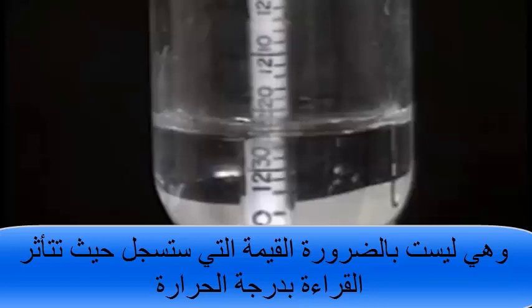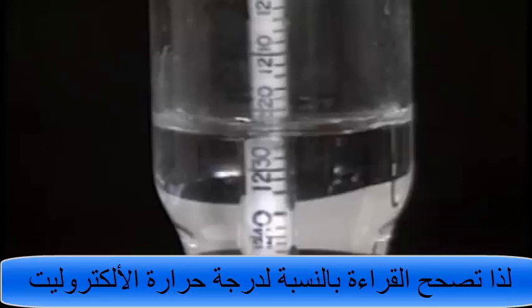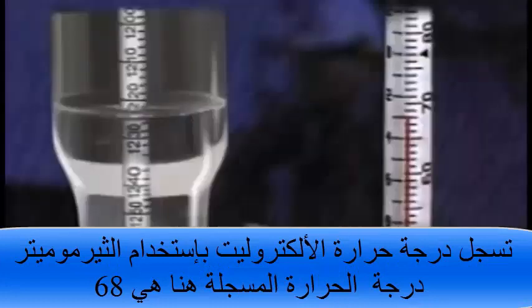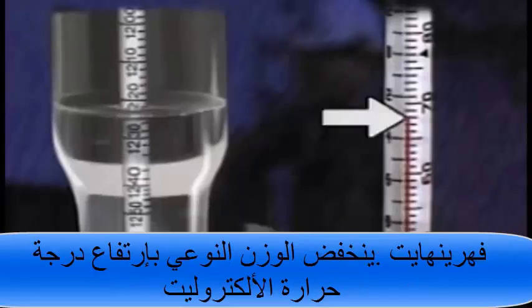This is not necessarily the value that's recorded. Specific gravity is affected by temperature, so the reading may need to be corrected for the temperature of the electrolyte. Electrolyte temperature may be checked using a cell thermometer. Here the cell temperature is 68 degrees Fahrenheit.